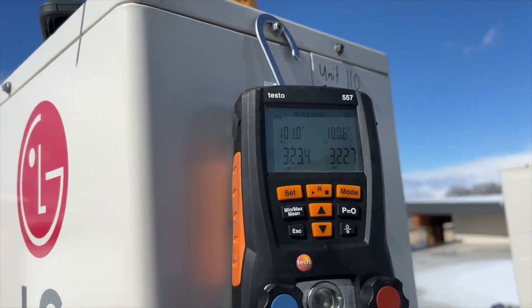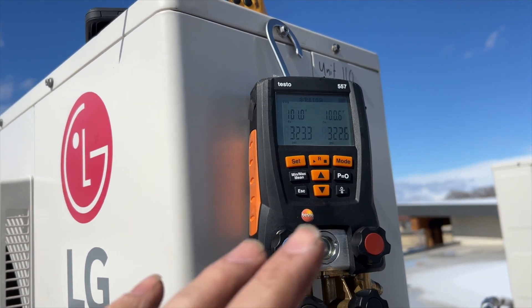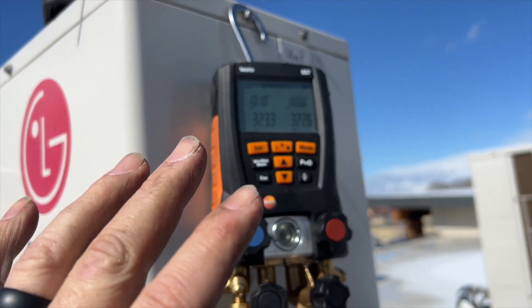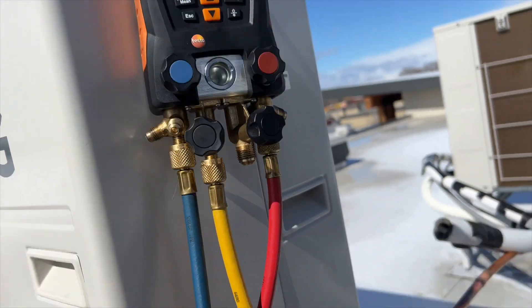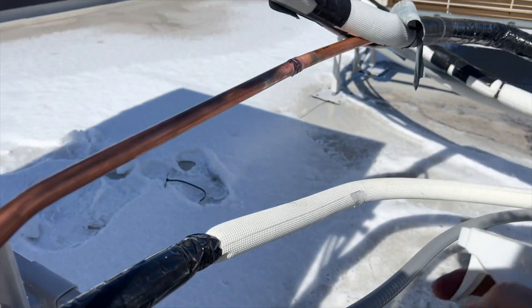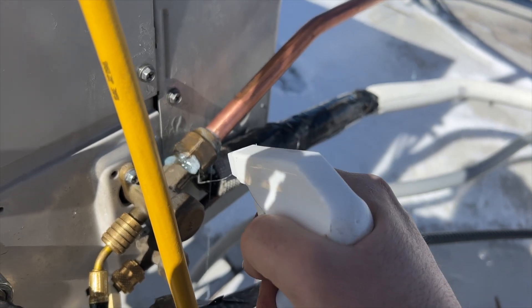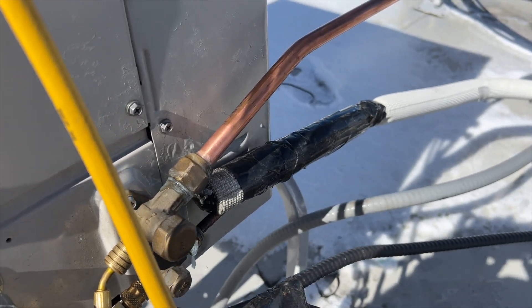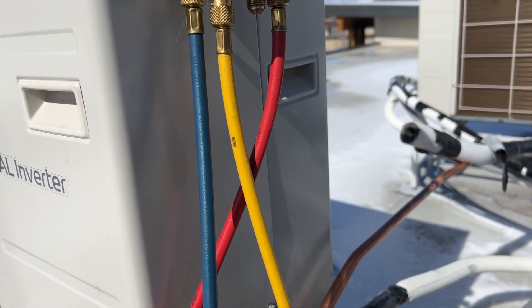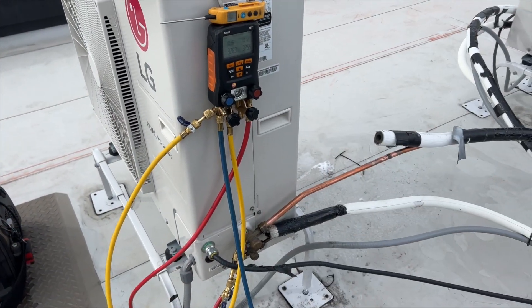Pressurized to about 323 psi. I just finished filling it so I'm going to let it settle for a good 10 minutes before starting the timer. I've already sprayed bubble solution on everything and I don't see any leaks here. If there are more leaks they'd be in the wall — really hoping there aren't. Going to wait 10 minutes and then start the count.